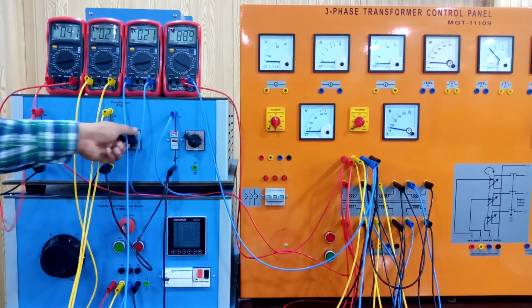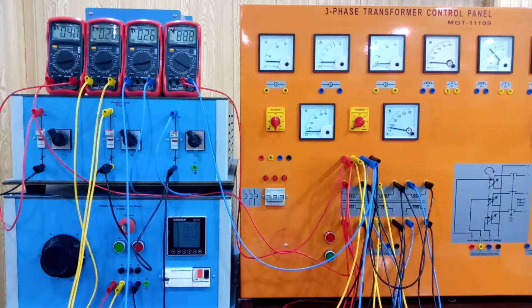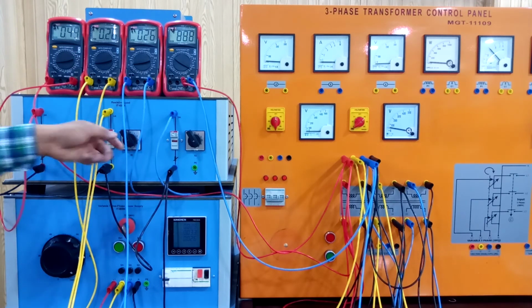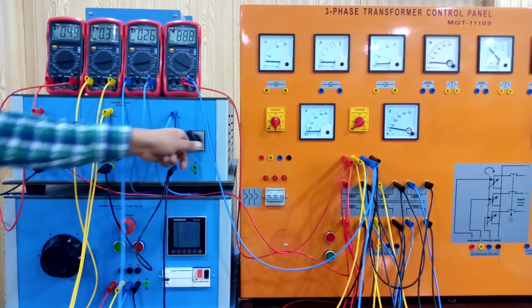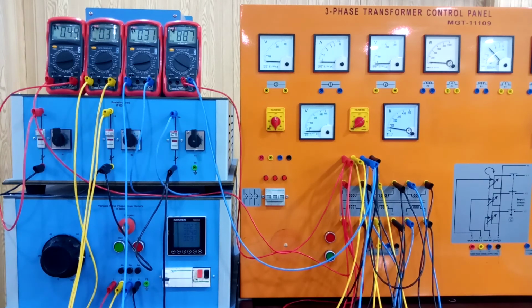For the fifth reading, we have 0.4 on the first phase, 0.26 on the second and third phases, and 88.8 volts. As you can see, the first phase is drawing more current from the supply, and the voltage keeps decrementing as we increase the load.